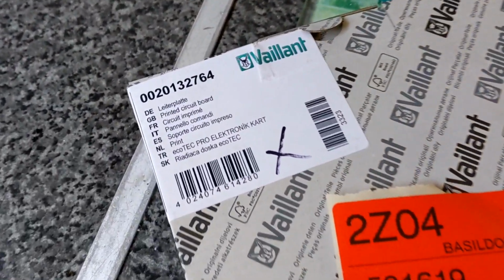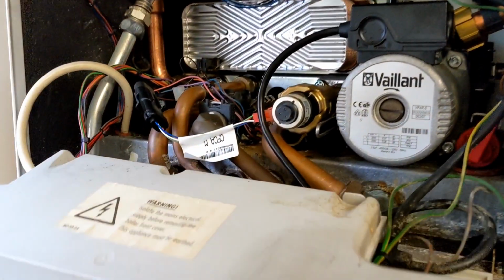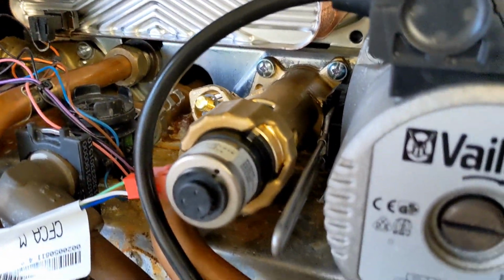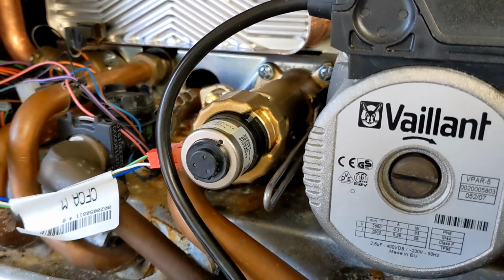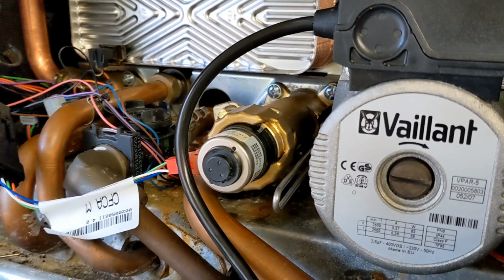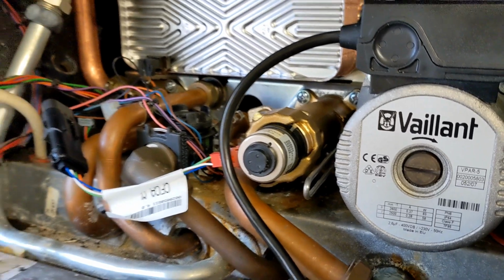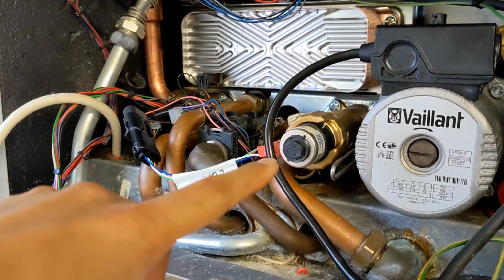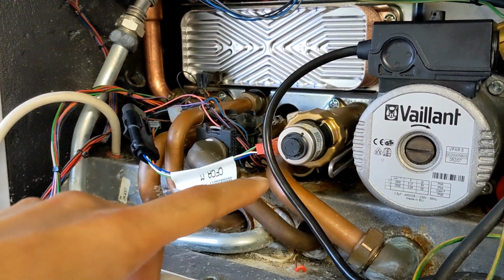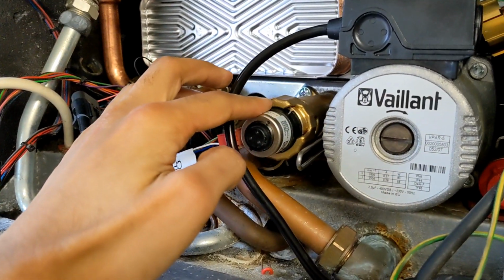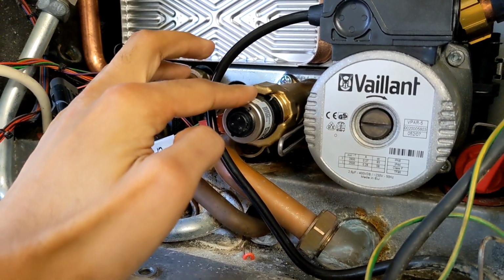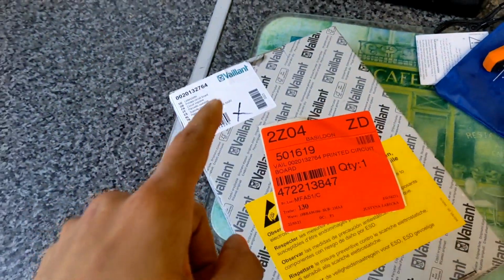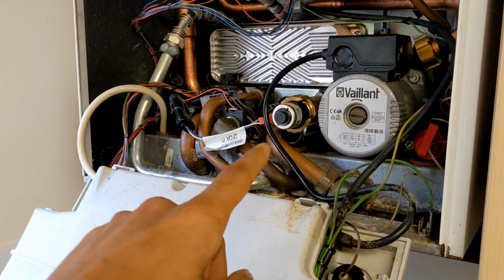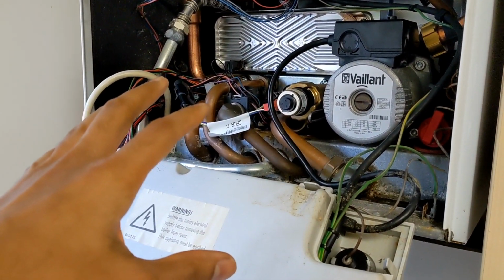Right, just to let you guys know, after I've done all that work, the diverter valve head wasn't moving. So that's a new diverter valve. I got another one out the van and I swapped the motorized head round to see if the spindle was moving in and out, and it still wasn't. So the only thing it could be, I thought maybe it was a faulty new one out the box. So when I swapped it over for a new one, it was still doing the same thing. The only thing that it could have been is a faulty PCB. Change the board over, diverter spindle starts moving, and we've now got exactly what we need.